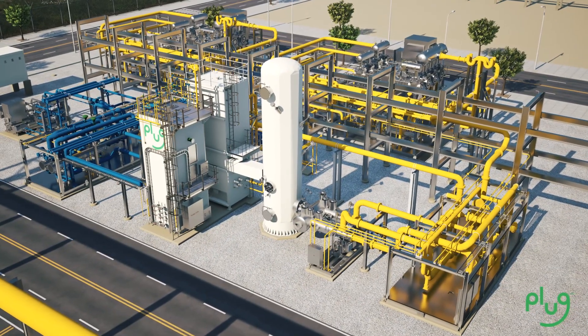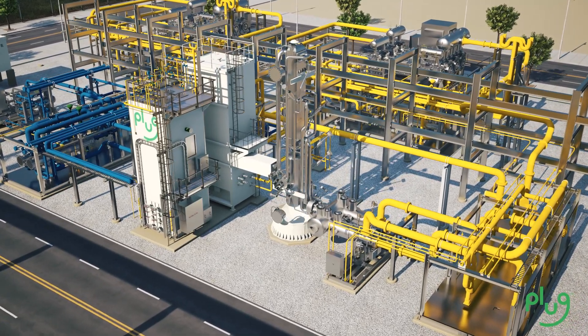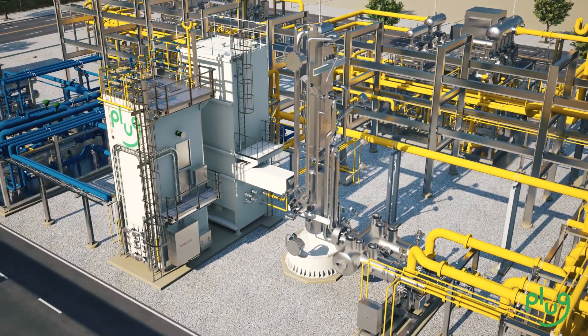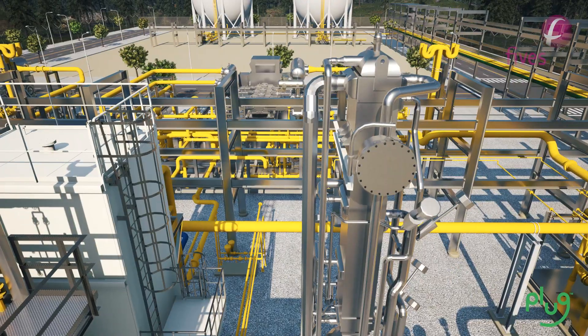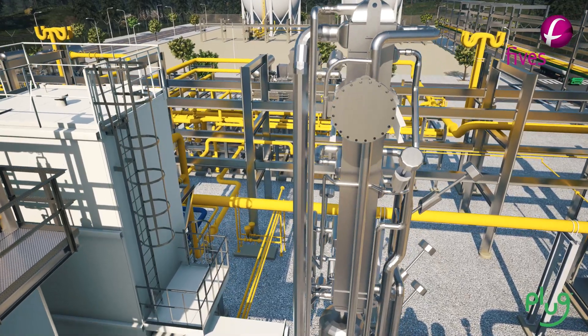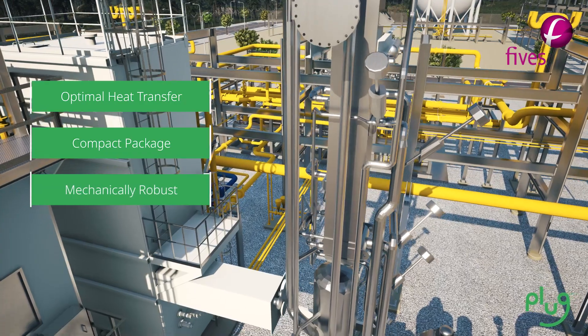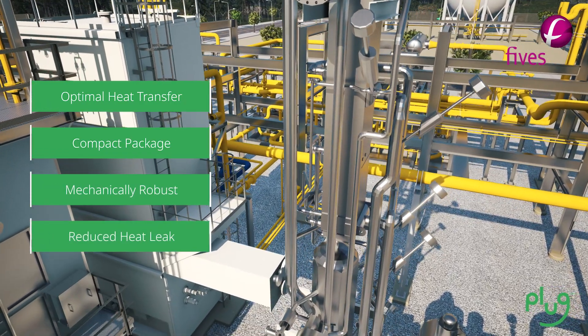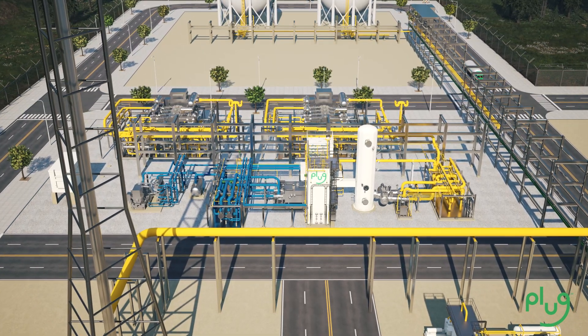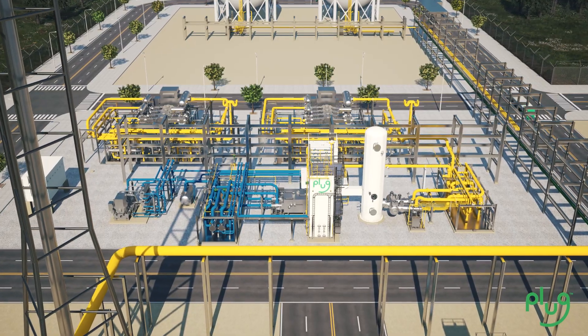At the core of the liquefier is our perlite cold box and a state-of-the-art vacuum cold box that each house a heat exchanger core supplied by Fives. Fives' experience in brazed aluminum heat exchanger cores provides optimal heat transfer in a compact package, ensures mechanical robustness, and reduced heat leak. The result is a highly responsive liquefier with a specific energy consumption below 11 kilowatt-hours per kilogram.